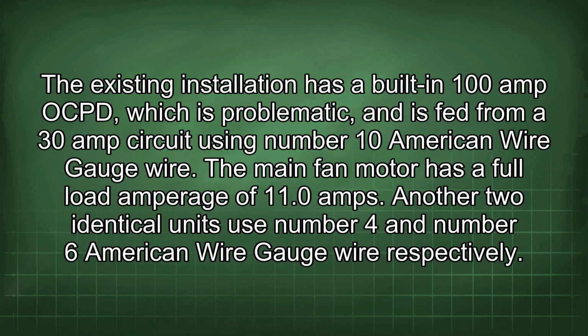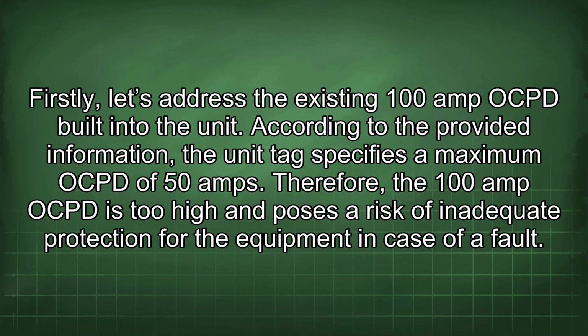The main fan motor has a full load amperage of 11.0 amps. Another two identical units use number 4 and number 6 American wire gauge wire respectively. Firstly, let's address the existing 100 amp OCPD built into the unit. According to the provided information, the unit tag specifies a maximum OCPD of 50 amps.